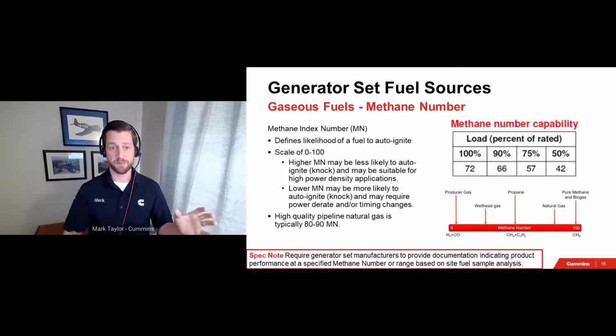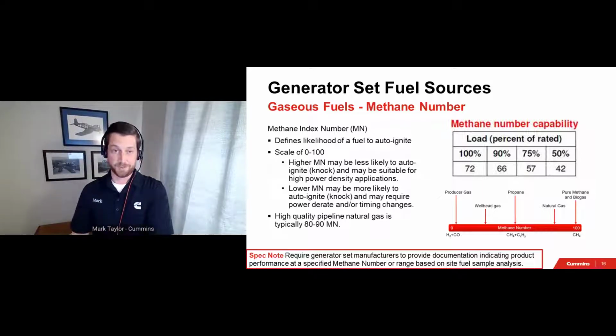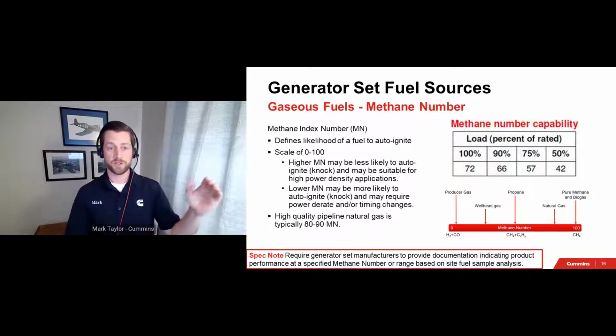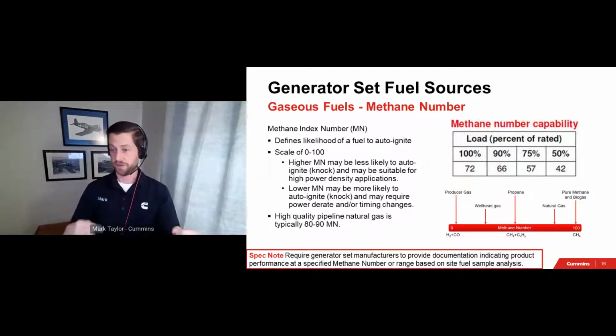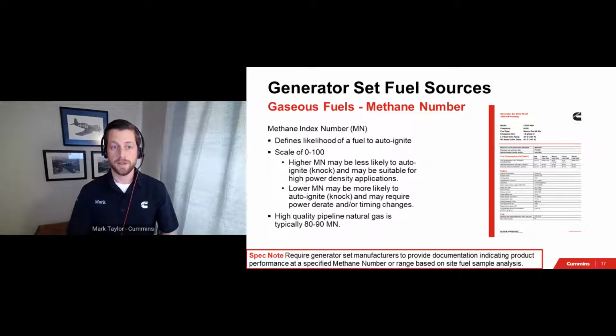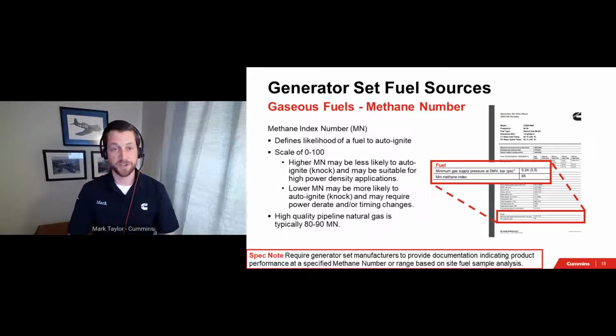So let's connect the dots between my first spec recommendation I provided earlier about seeking out the fuel's methane number with a fuel analysis whenever there's any doubt about its quality. Knowing the properties of the methane index number of a fuel, one should be able to draw a straight line from that value to a generator set manufacturer's data sheet in order to make sure that the product is able to run optimally. This confirmation should be an expectation on the manufacturer's data sheets, so it's up to us to make that available for you. And we offer that right on page 1 of our gaseous fuel generator sets. It's not hiding anywhere.